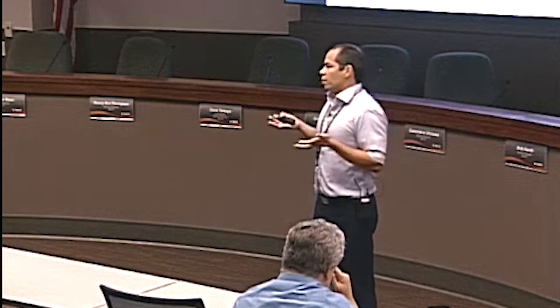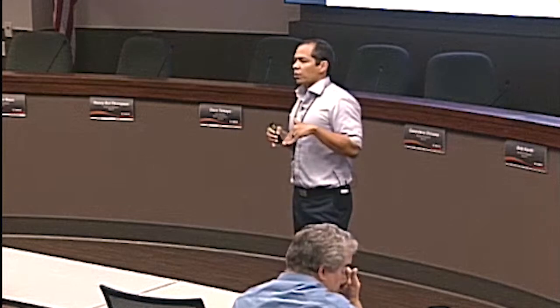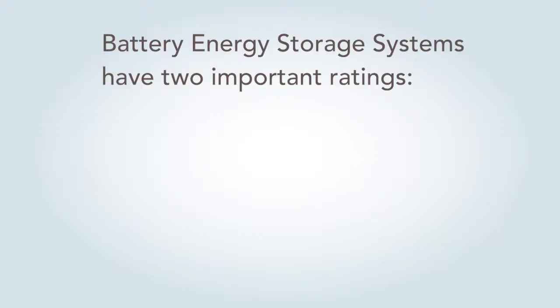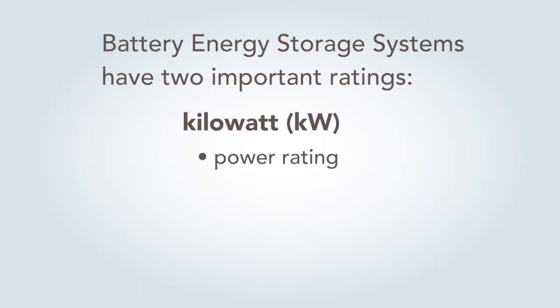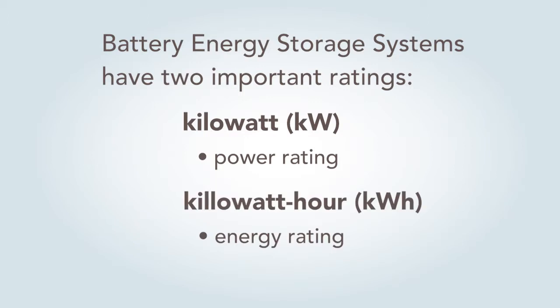Commercial is primarily going to be a financial decision, right? You're going to be trying to do demand charge management. With a battery energy storage system, I want to point out that there are two key factors, and this is really understanding power versus energy. You'll see it has a rating, right? It says, oh, it's a 30 kilowatt system, 60 kilowatt hours. What's the difference between a kilowatt and a kilowatt hour?